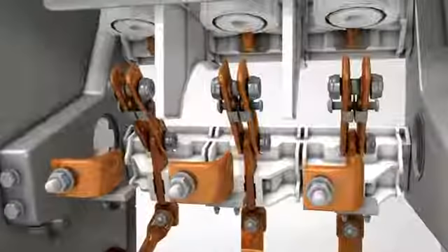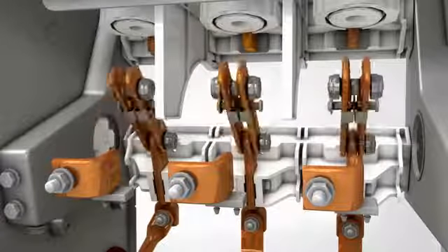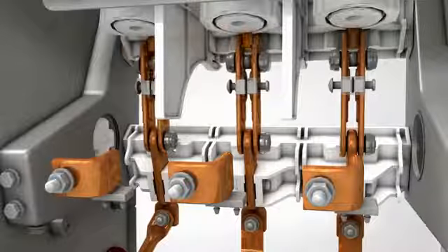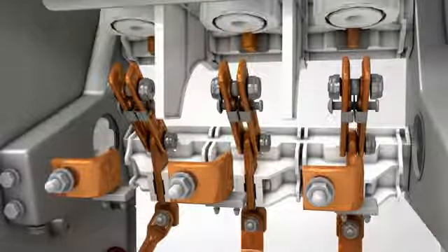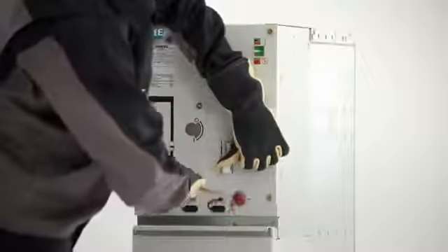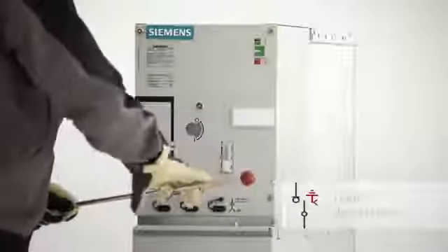This device combines a switch disconnector and an earthing switch. Its mechanical construction completely prevents accidental earthing when the feeder is energized. De-earthing and re-energizing the feeder is easy, using the appropriate operating lever for each process again. So, switching is both simple and safe.